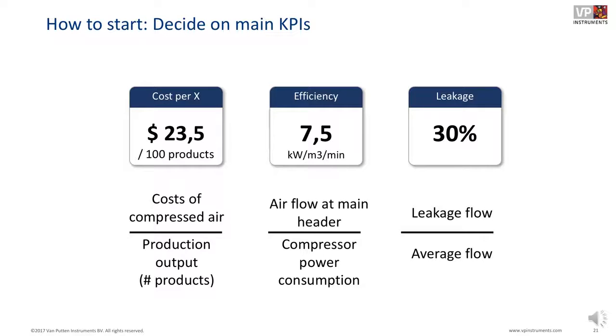Determine some KPIs. Don't overdo it by determining 20 KPIs from the moment that you start. Just come up with a couple. Maybe your cost per X. X can be tons produced products. Or your cost per SCFM used. Or the efficiency of the machines if that's where you're after. If you're running with old machines and you're interested in how they are running and how they perform and you want to stay on top of that, then you can do that.